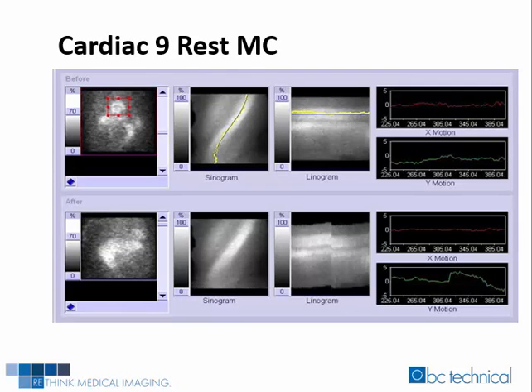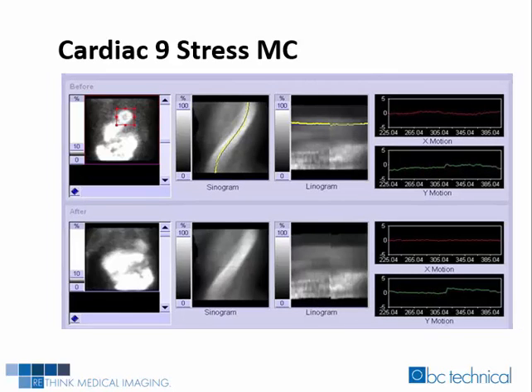Cardiac 9's resting study showed around two pixels of motion. The motion-corrected dataset exaggerated the motion and displayed over five pixels of motion after automatic motion correction was applied — increasing the motion from two to five pixels. Cardiac 9's stress study showed greater than two pixels of motion before automatic motion correction was applied. The motion-corrected dataset displayed relatively the same two-pixel motion as the non-corrected dataset.